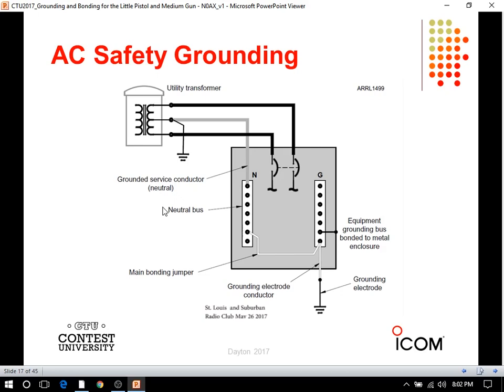Where I am, they don't care, you know. I asked my electrician, I said, what happens if I put in some more ground rods? He says, can't never have too many grounds. So, all right, I'm going to put in some. All you've got to do is drill a hole through the blocking and run a piece of number 6 from your ground right here. There's probably a big terminal right on your service box. Run it right outside, right to the ground rod, a few feet away.